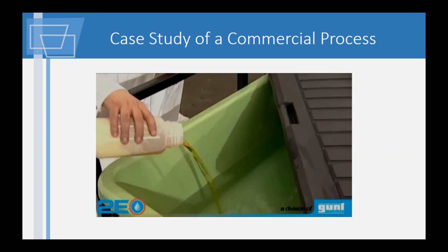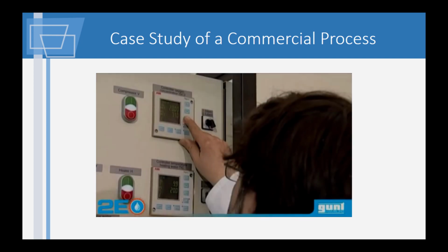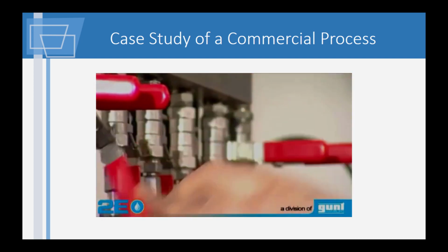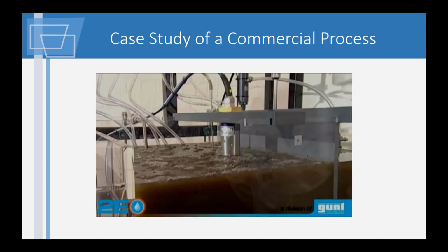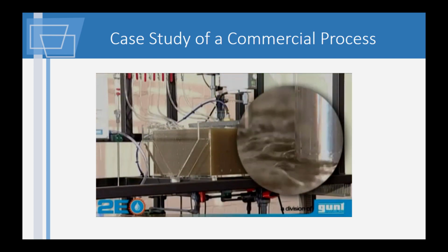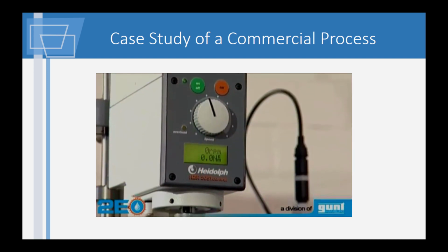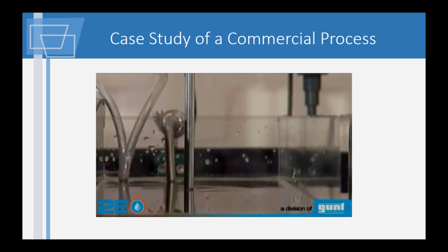Artificial wastewater is prepared in the laboratory to simulate average contaminated domestic wastewater. After the desired oxygen concentration has been adjusted, the aeration can be started. Under aerobic conditions, the microorganisms degrade organic matter and nitrify ammonia to nitrate. To enable also a denitrification, an anoxic section is installed in the aeration tank.